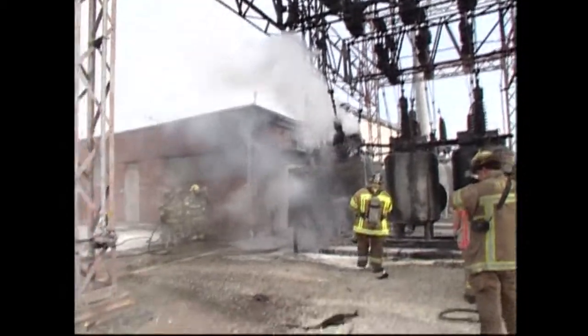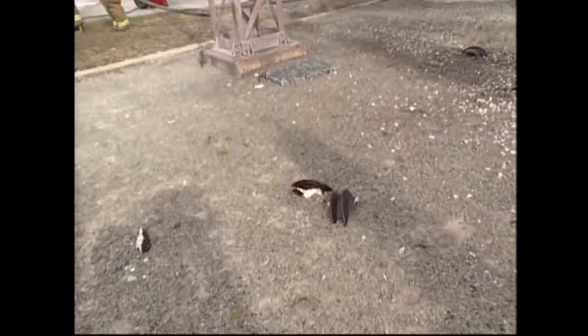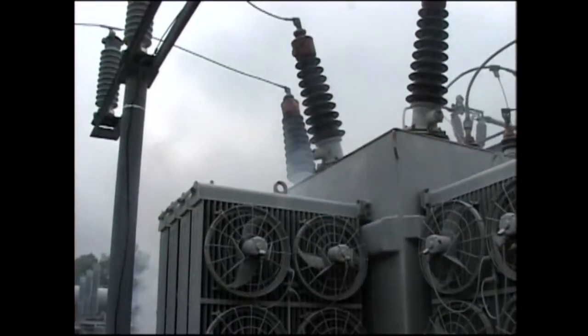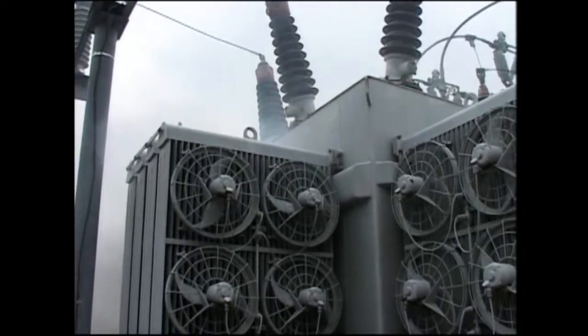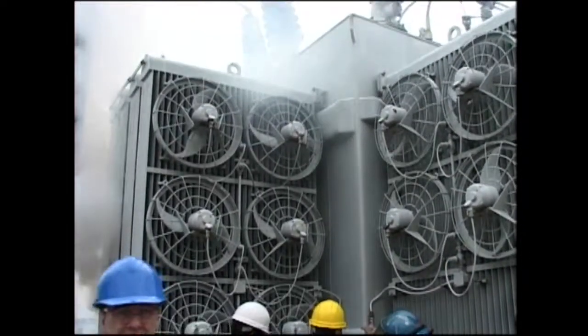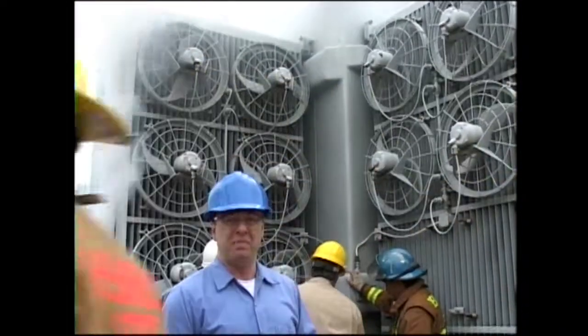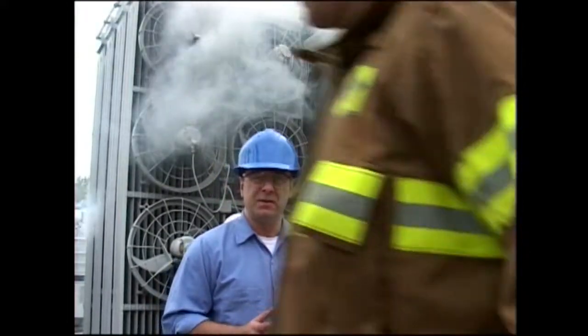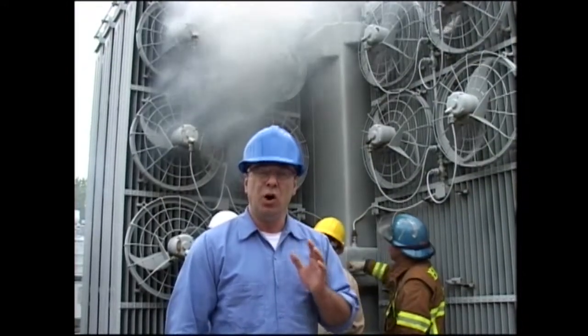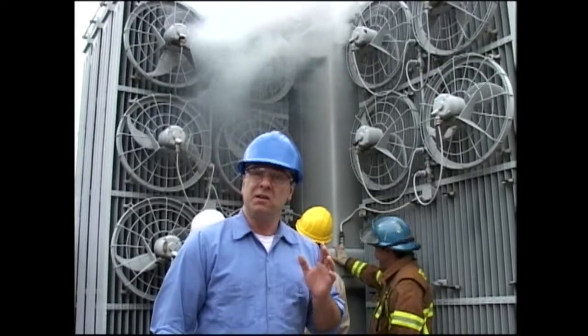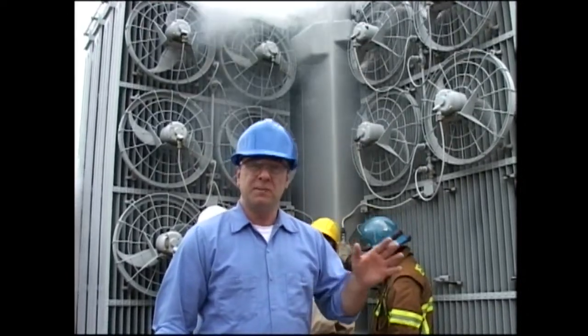Another danger, glass and ceramic insulators under intense heat can explode when water is applied. There are other hazards to be aware of, such as toxic gases which can arise from insulation in batteries. So it's best to limit the number of people involved to only the most essential and to confine the fire within the substation fence line.